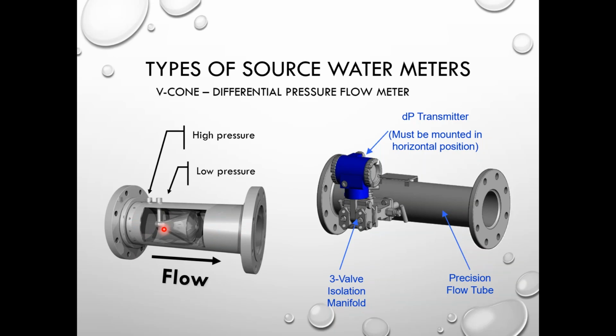The size ranges are from like 1 to 2 inches. This again is a 0.5% accuracy. And generally, again, the turn down ratio or the range is limited. It's about a 10-to-1 turn down ratio as well.